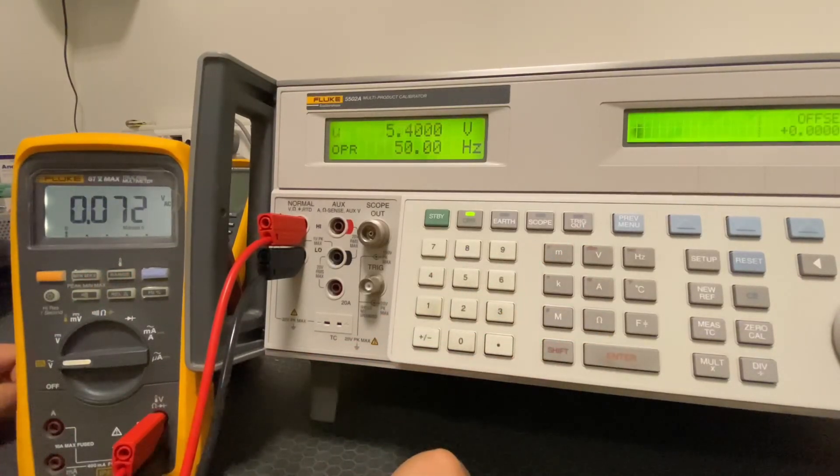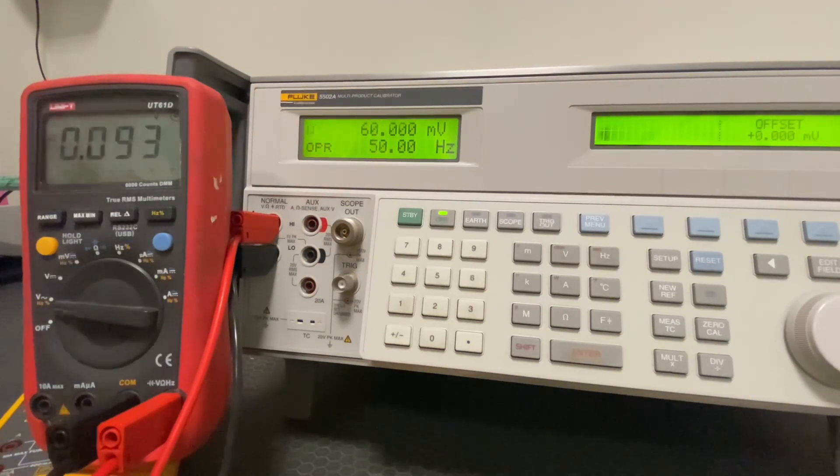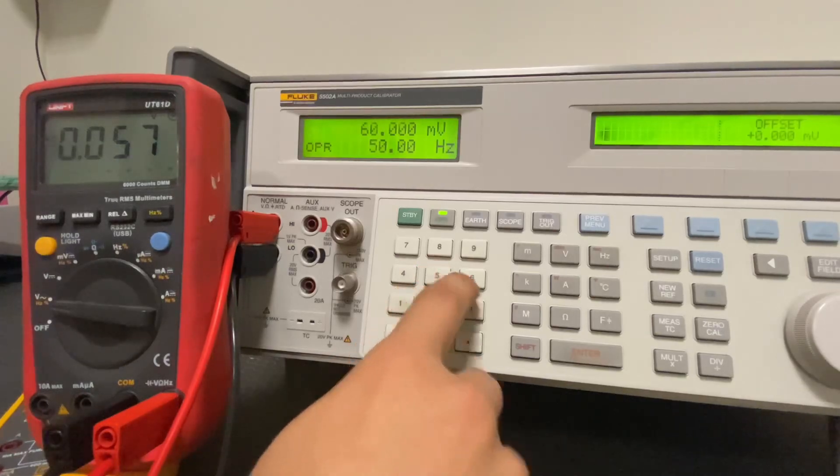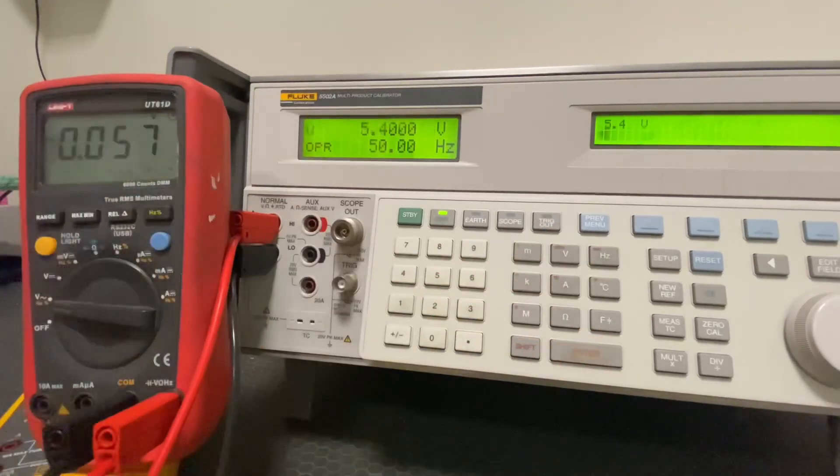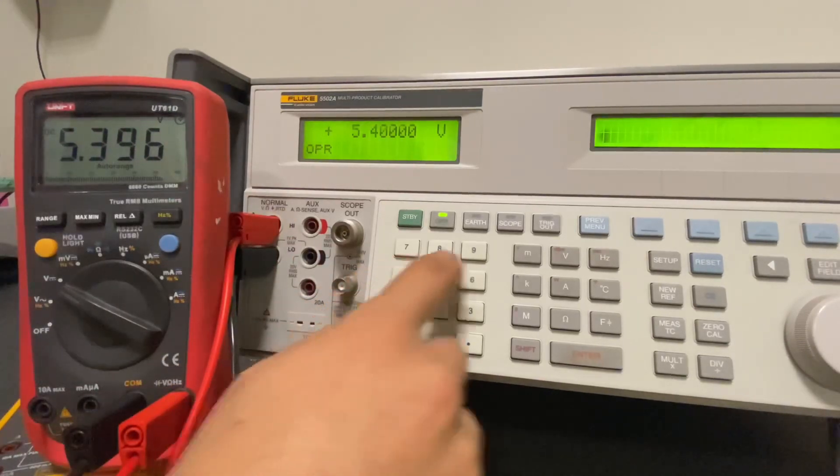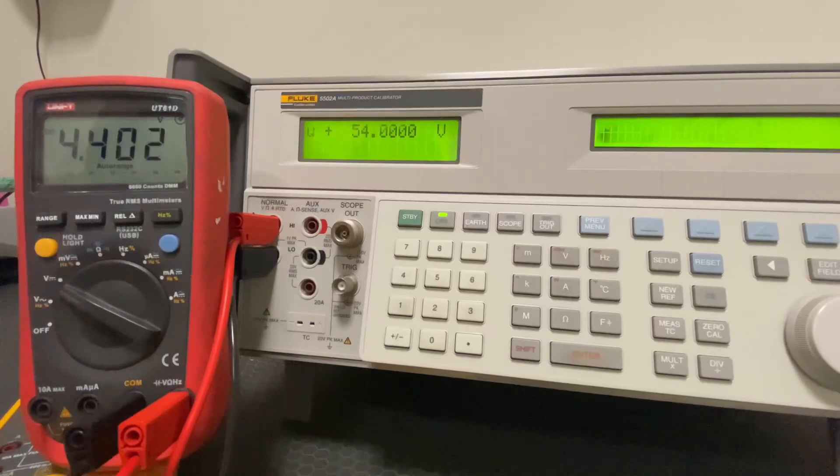We will check our measurements at 50 hertz. While the Fluke shows no deviation at 60 millivolts, the UNI-T shows a value that's 3 millivolts lower. Let's check the 5.4 and 54 volt values. Don't forget to subscribe to my channel for more videos like this.